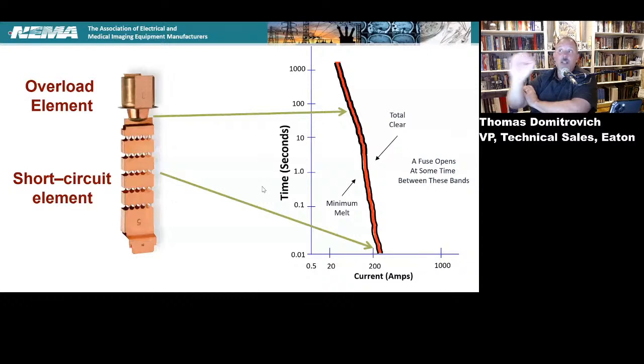And it's a science unto itself to know exactly how to construct that piece of the pie to get the curve that you need, to meet the UL standards, because they'll tell you a couple data points that you have to hit, or not be greater than, so to speak. But everything else, you have flexibility. So manufacturers will try to create a trip curve.